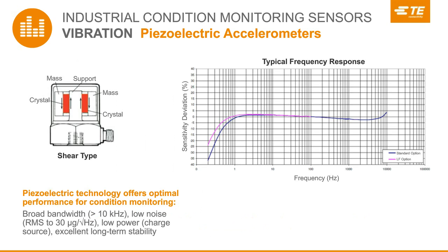We've talked about using an accelerometer for vibration monitoring, but how does an accelerometer actually work? Here's a cross-section of a typical packaged plug-and-play component. There's a central support pillar, a cylindrical piezoelectric sensing element, and around that there's a concentric inertial mass. If we shake this structure up and down in the vertical plane, inertial force exerts shear stress on the piezo element, and we see the electrical response to this. If we shake it in the horizontal plane, we get no output at all. Many of our accelerometers for condition monitoring are built using this general construction. Some of the smaller board mount components have different internal geometry, but still rely on inertial forces exerted on a piezoelectric crystal.